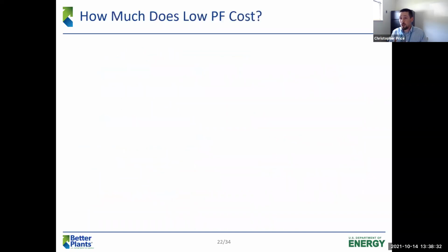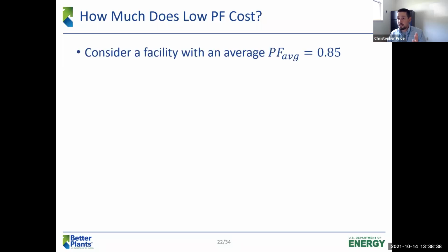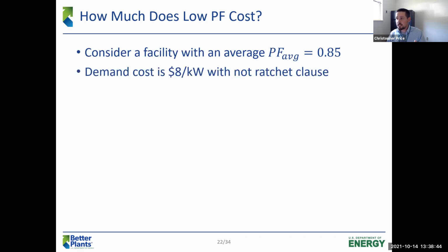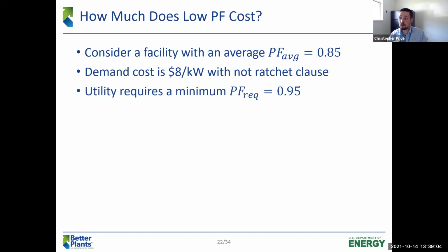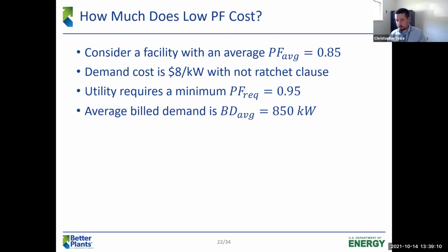So how much does a low power factor cost you? Run through a quick example here. Consider a facility that has an average power factor of 0.85. The demand cost is around $8 a kilowatt. There is no ratchet clause. If there was a ratchet clause, the cost would be greater because your billed demand, that ratchet demand, could be adjusted upward by the power factor adjustment. The utility requires a minimum power factor of 0.95, and the average billed demand is 850 kilowatts. In this example, they're billed on kilowatts.